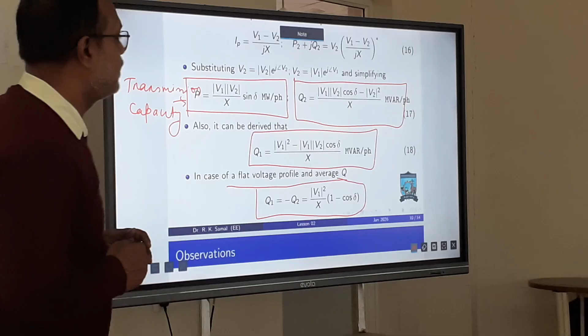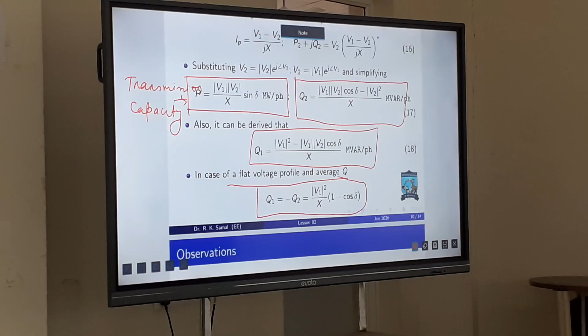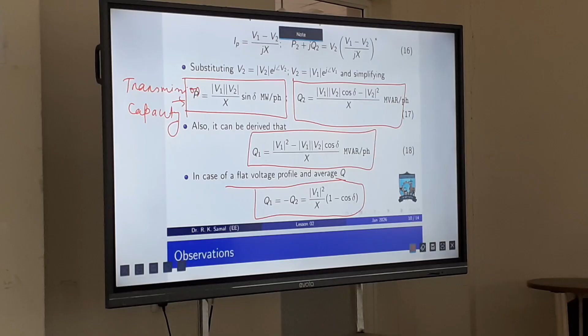Okay, two cases we have considered. Case one, when voltage was allowed to vary, which is not a practical case. Voltage is never allowed to vary. The other one is when voltage remains constant. So that is a normal situation, under which you have now concluded that the transmission capacity or the static stability limit of a transmission line is given by the formula V1 V2 by X sin delta megawatt per phase. It is a per phase one.